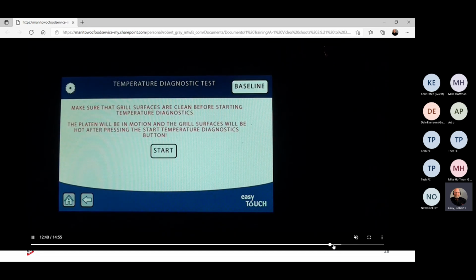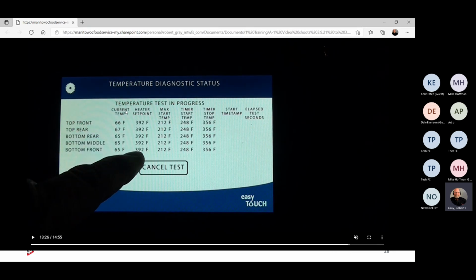So again, starting at temperature diagnostics, click on that, and you'll see your current temperatures. You'll see your heater set points, what each lane is set for the temperature. The max start temp, okay? Your current temperature needs to be below 212 degrees in order for the temperature diagnostics to start. So again, 66, 67, 65 is all below 212. If I had 214, it's not going to start until it gets below 212, all 5 zones. Once it's below 212, it'll start to heat back up again. And again, make sure that you're doing this from the off mode. If it's a heater set point and you're in preheat, it's going to heat to that point.